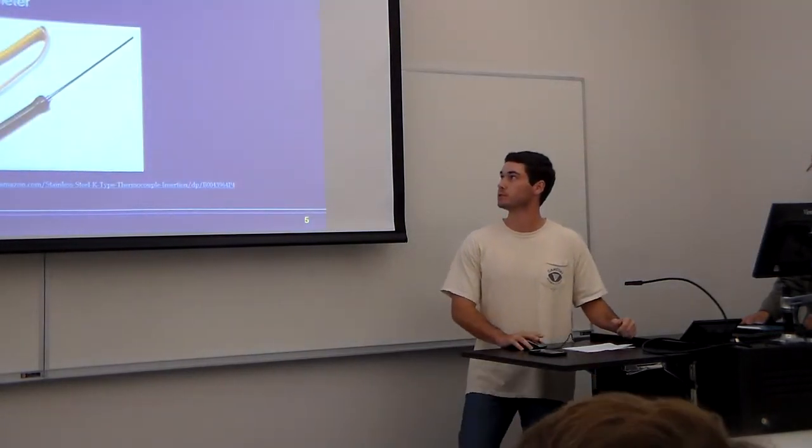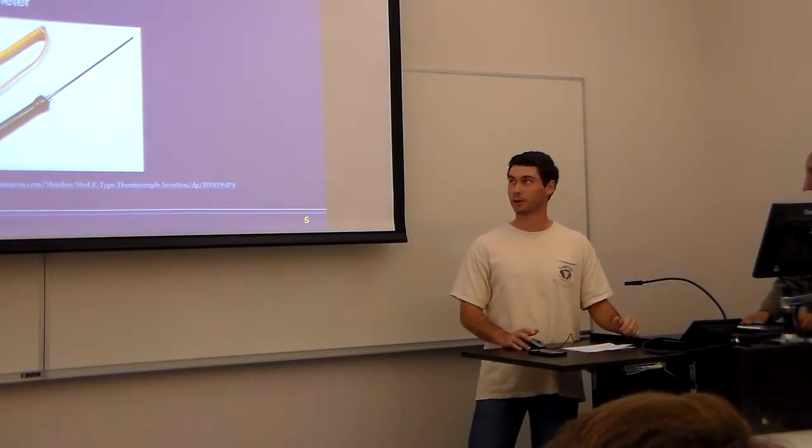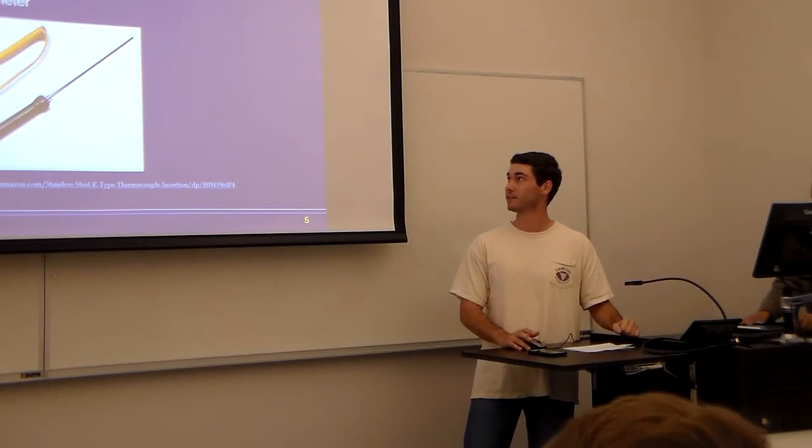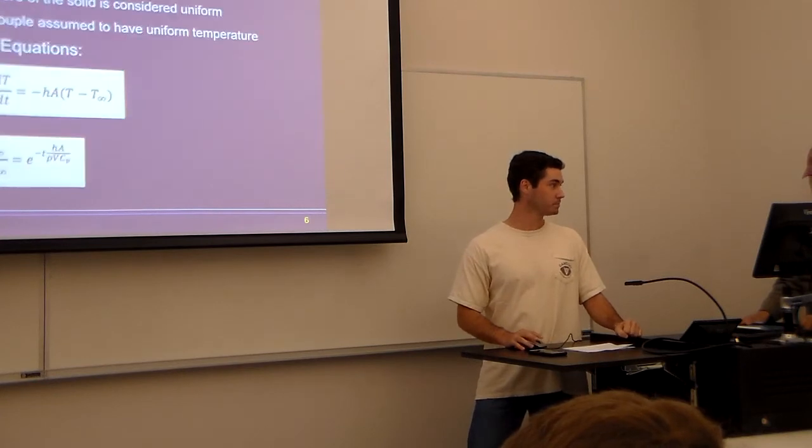So the main instrument used was the type K thermocouple. The approximate range is about -400 degrees to over 2,000 degrees Fahrenheit. And this particular thermocouple had a 1/8 inch diameter.